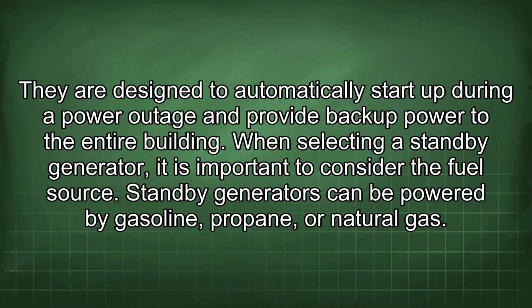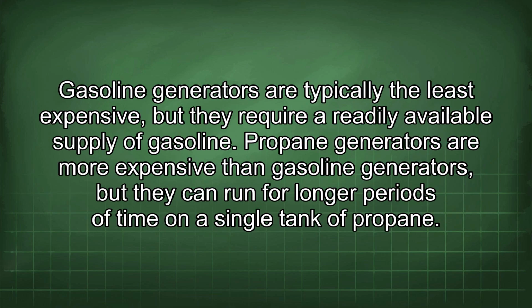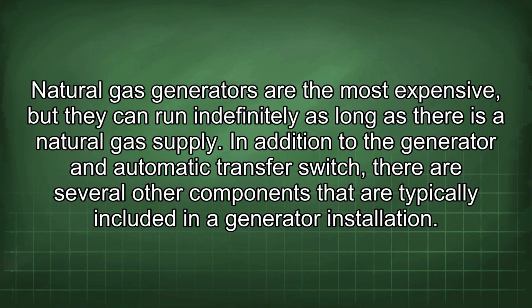When selecting a standby generator, it is important to consider the fuel source. Standby generators can be powered by gasoline, propane, or natural gas. Gasoline generators are typically the least expensive, but they require a readily available supply of gasoline. Propane generators are more expensive than gasoline generators, but they can run for longer periods of time on a single tank of propane. Natural gas generators are the most expensive, but they can run indefinitely as long as there is a natural gas supply.